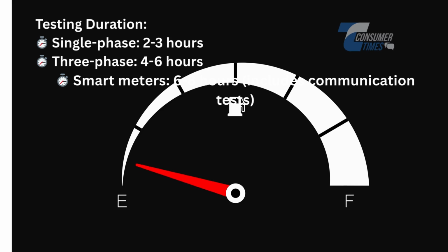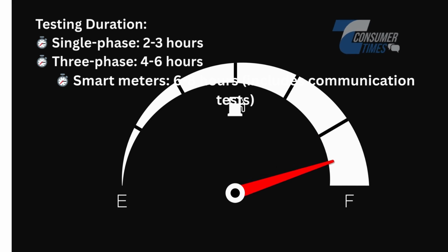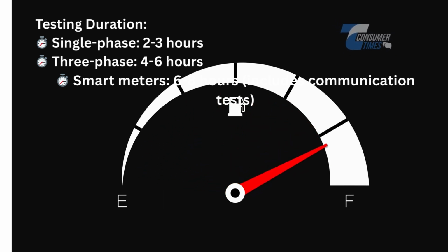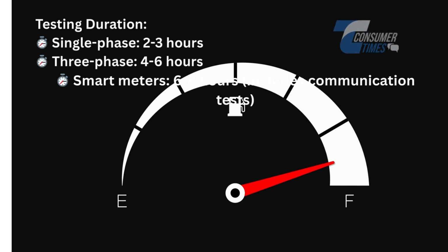This creates a chain of traceability that ensures every energy meter in the field is ultimately referenced to the same fundamental standards. As a consumer, you have the right to request meter testing if you suspect your bill is incorrect. Most utility companies have procedures for this. In India, electricity distribution companies are required to test meters periodically as per State Electricity Regulatory Commission guidelines. Typically, meters are tested every 5 to 10 years depending on the type and regulations.